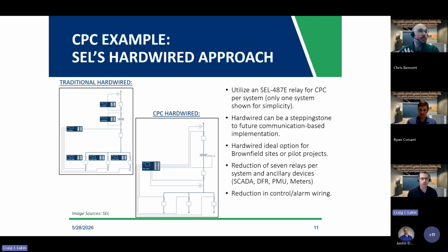The key benefits here is obviously you're reducing the relays, and as you can see, we're going from 6 relays on the left to 1 relay on the right. But I'll note that we have a reduction of 7 relays per system. I'll explain that a little bit. In the example on the left, we're already showing some combined functions in those relays, such as the line relay on the top performing breaker control functions, and the bus relay likely performing breaker control functions.